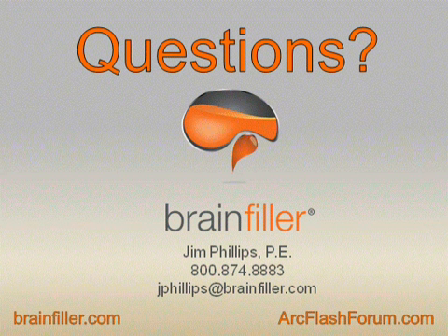There's another question about arc flash analysis. Are these going to be required for all new installations, modifications and upgrades? Actually, the arc flash hazard analysis, NFPA 70E, the interpretation that many are familiar with is this: it's safety, and safety is now. So there's a requirement that the arc flash hazard analysis applies to everything that's listed within Article 90 in NFPA 70E. Now, how you go about it, there are two different methods. You can go through the full-blown calculations, the incident energy analysis, or use the hazard risk tables as another method.